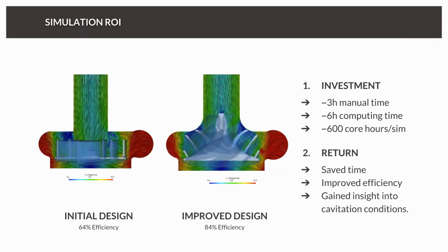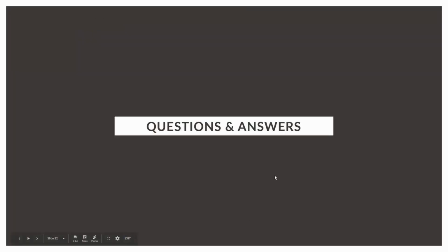Yes, and the return for us was, first of all, we saved time. Just think about if you want to test something on the physical test rig, how much more time and money it would cost you to prepare the model and the rig. Overall, we were able to massively improve our design efficiency. It's now 20% higher. And we also were able to show that cavitation is not a big problem for our design, and we gained some insights into the cavitation conditions.